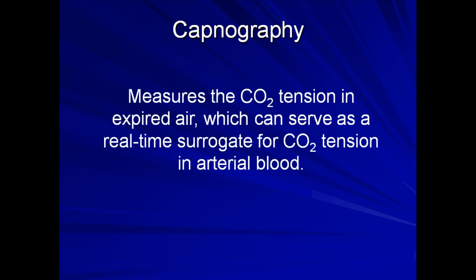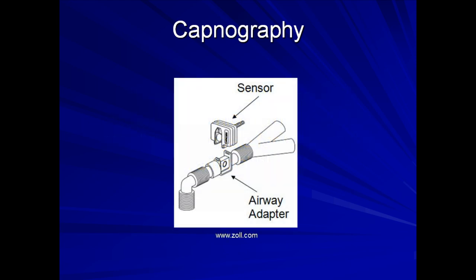Now let's move on to capnography. Capnography provides a continuous measurement of carbon dioxide tension in expired air, which can serve as a real-time surrogate for carbon dioxide tension in arterial blood. Most capnography utilizes infrared spectrography: an emitter and photo detector are placed along the ventilator tubing. The emitter produces light in the infrared spectrum, and certain wavelengths are selectively absorbed by carbon dioxide — the less light detected at those wavelengths, the greater the concentration of interposed carbon dioxide. This is a similar principle to that used in pulse oximetry.